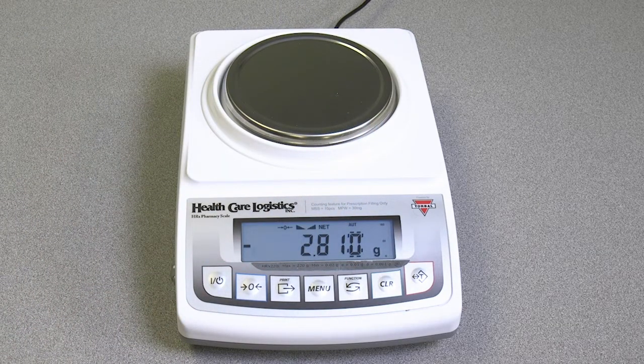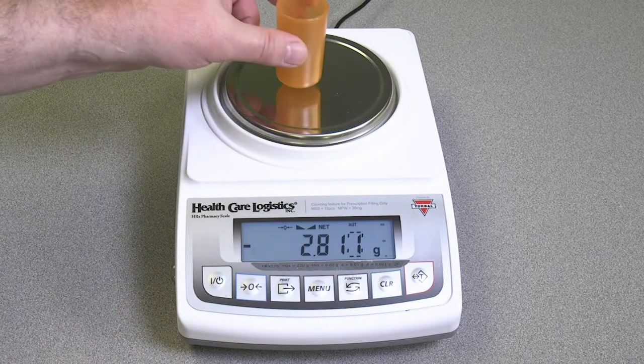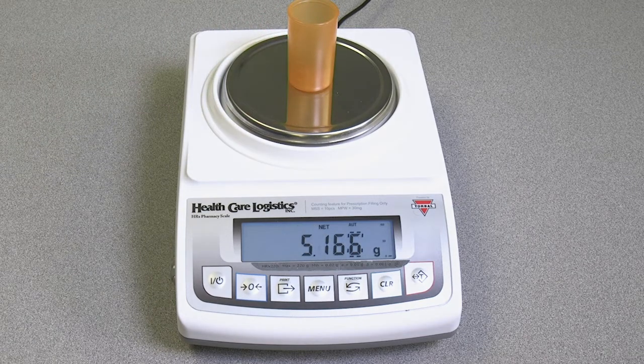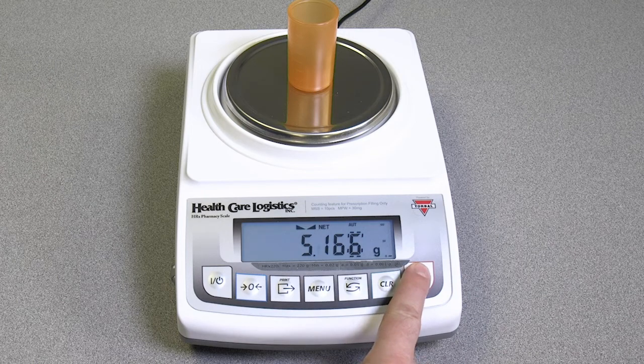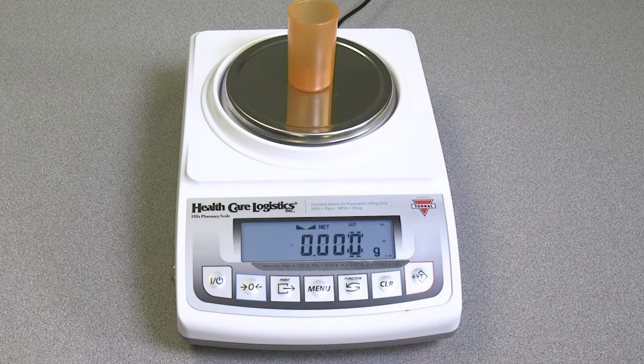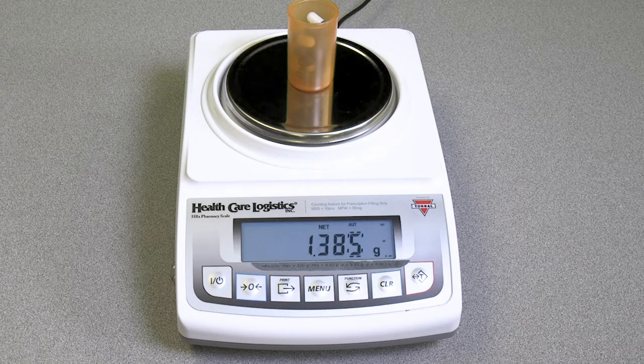With the scale already in weigh mode, place the empty new container on the pan. Wait for the stabilization notification to appear on the display. Press the T key. Wait for the scale to finish taring. Verify the weight is 0 and the net notification is displayed. You can then proceed to weigh additional product.